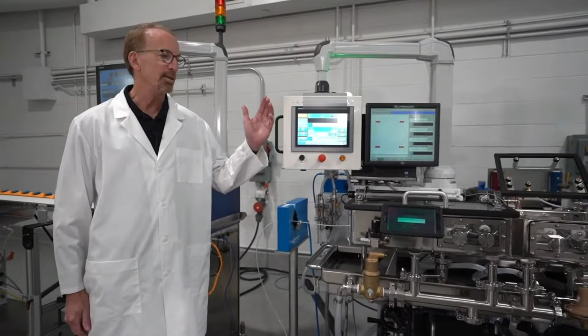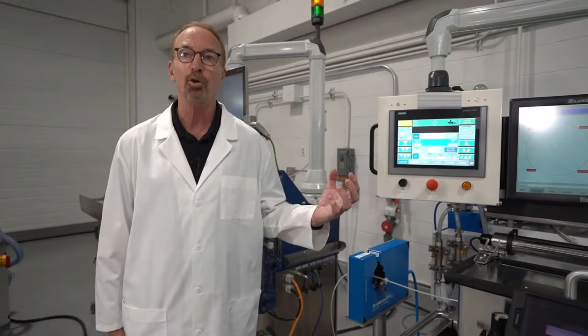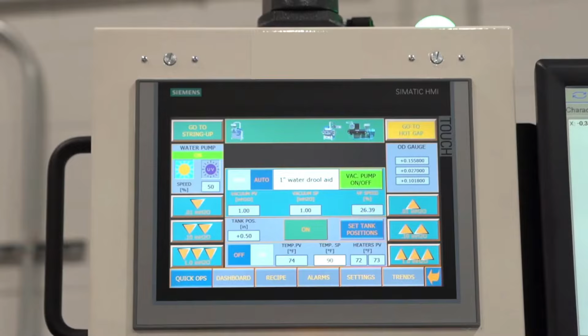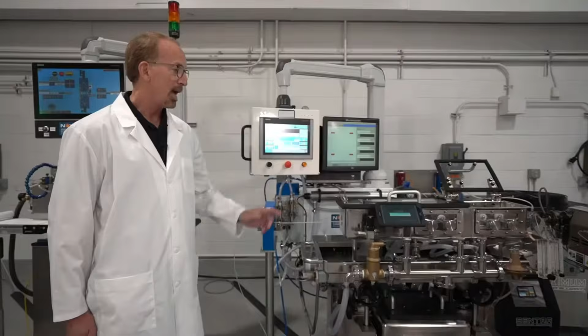Everybody in medical knows the hot gap, the actual distance between the face of the hot die and where the tube enters the water, is a critical validation point. That distance should be measured as it can change the properties in your medical tube, which are highly critical. So as you'll see, I can simply push on our touchscreen, press go to hot gap, and it will go exactly right to the thousandths of that hot gap. A very critical feature that we feel had to be repeatable.